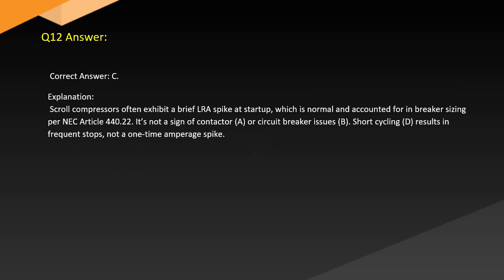Answer. Correct answer: C. Explanation. Scroll compressors often exhibit a brief spike at startup, which is normal and accounted for in breaker sizing per NEC Article 440.22. It's not a sign of contactor (A) or circuit breaker (B) issues. Short cycling (D) results in frequent stops, not a one-time amperage spike.